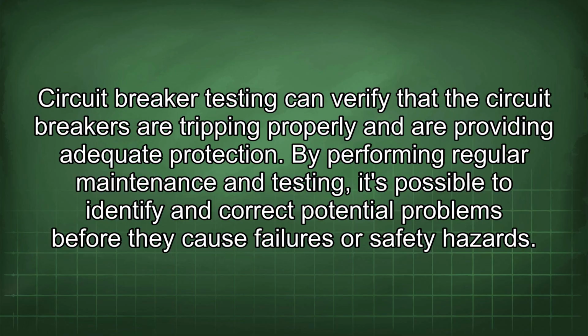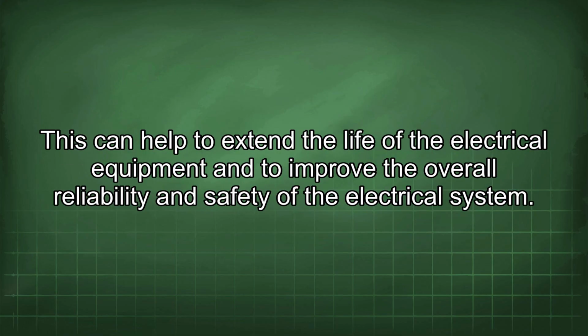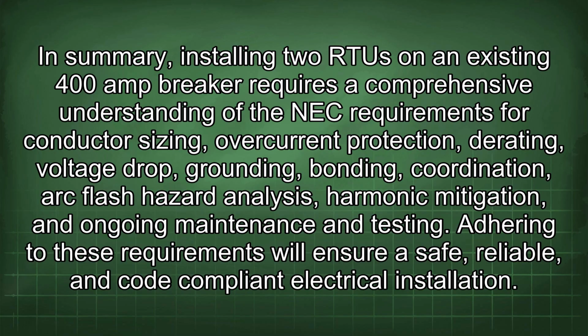By performing regular maintenance and testing, it's possible to identify and correct potential problems before they cause failures or safety hazards. This can help to extend the life of the electrical equipment and to improve the overall reliability and safety of the electrical system. In summary, installing 2 RTU on an existing 400 amp breaker requires a comprehensive understanding of the NEC requirements for conductor sizing, overcurrent protection, voltage drop, grounding, bonding, coordination, arc flash hazard analysis, harmonic mitigation, and ongoing maintenance and testing. Adhering to these requirements will ensure a safe, reliable, and code-compliant electrical installation.